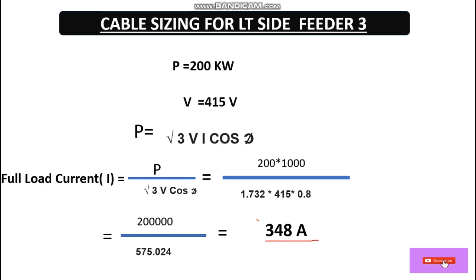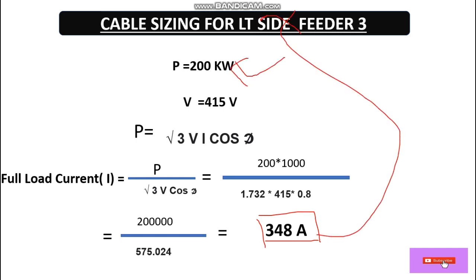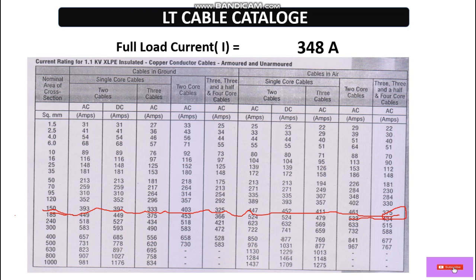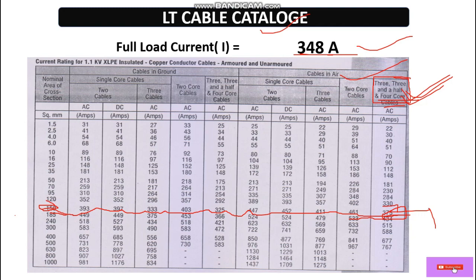Now let's move to the catalog. As per this full load current, which cable size would be feasible? We are going to lay the cable in ambient air — air site. Since this is a three-phase four-core system, looking at the catalog: 348 amperes falls between 330 and 375, so 375 amperes corresponds to a 150 square mm cable.